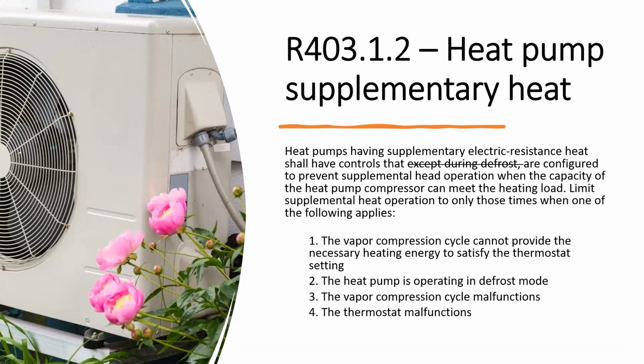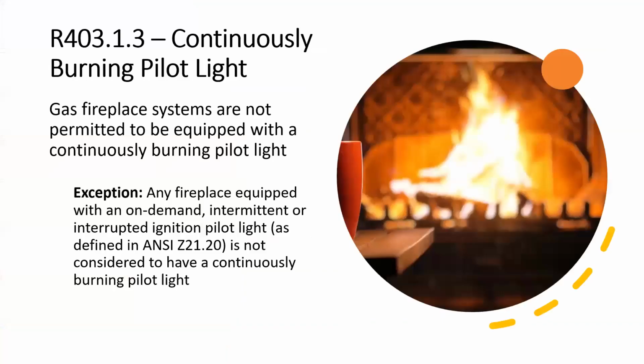It will have to remove the frost on the compressor to keep running. But then it actually comes down at the very bottom and says, limit supplemental heat operation to only those times when one of these meet. And now that's where they've put in when it's operating in defrost mode. So vapor compression cycle cannot provide the necessary heating, heat pump is operating in defrost mode, the vapor compression cycle malfunctions, or the thermostat malfunctions. Then it can bring on that supplemental strip heat. Otherwise, whatever controllers are in there need to not allow supplemental strip heat to come on unless you meet one of these four things that are happening.